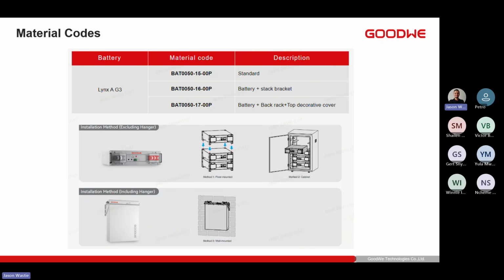These batteries can be installed either upright or horizontal. So we can install them in a cabinet, we can wall mount them, we can floor mount them, and there is a decorative cover that goes over the top of them. It is an IP20 rated battery, so it does need to be installed indoors. Being indoors in a household, if you want to make it look slightly more aesthetically pleasing, we can add in that top decorative cover to close off all the terminations, make it seem a bit neater, and make the installation a lot nicer and safer for the homeowners.